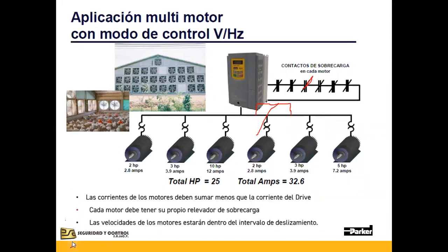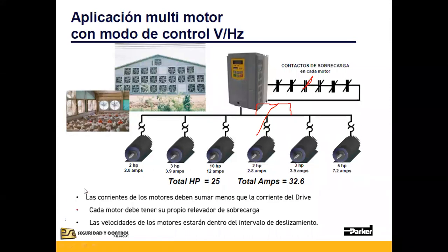Un punto importante: los relevadores de sobrecarga deben ser de tipo bimetálico o de aleación eutéctica, es decir, que trabajen directamente con la corriente. Como la salida del variador es PWM, no es una onda senoidal, si se pusiera uno de tipo electrónico pudiera no funcionar adecuadamente, ya que estos trabajan con transformador y están esperando la señal de 60 Hz. Al llegarle el PWM no van a funcionar correctamente. Un relevador bimetálico funcionaría perfecto en esta aplicación.